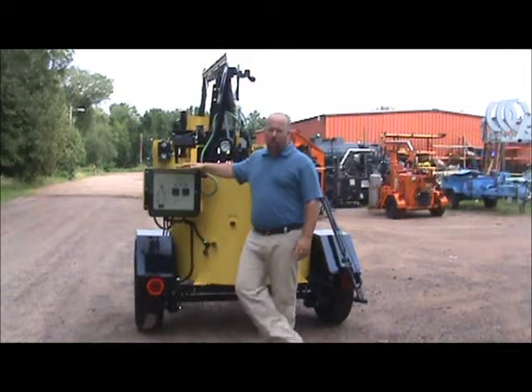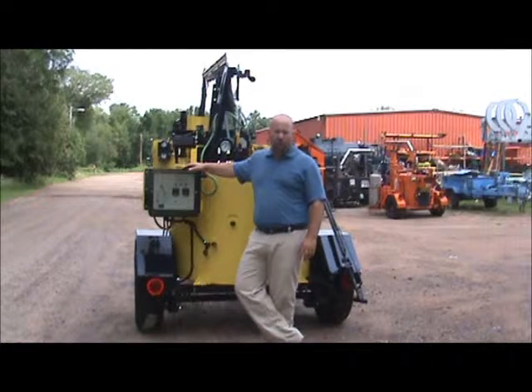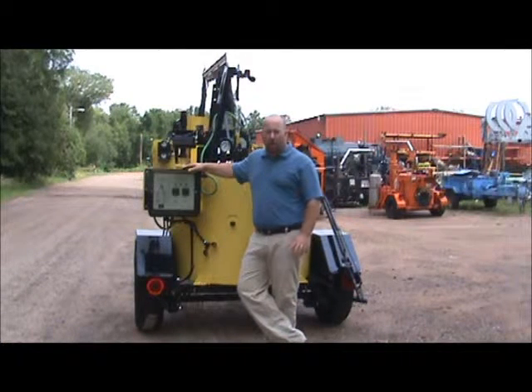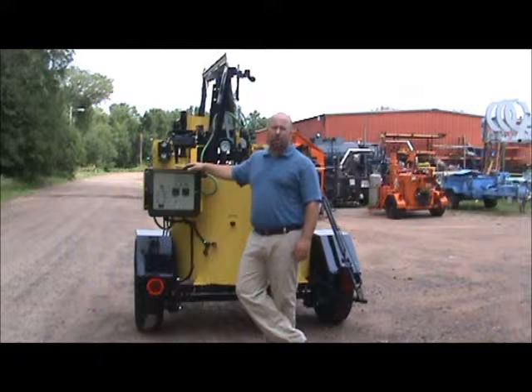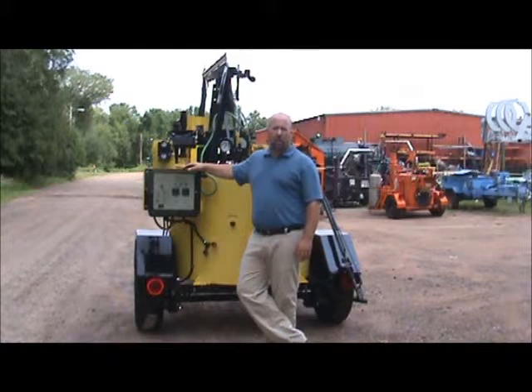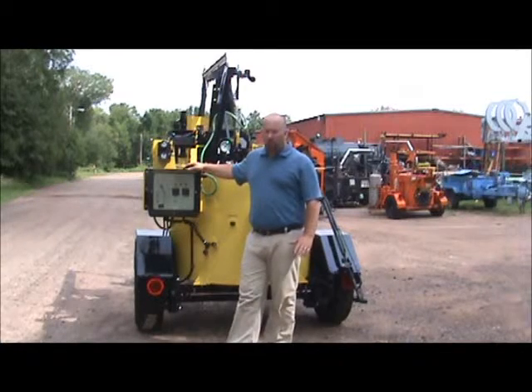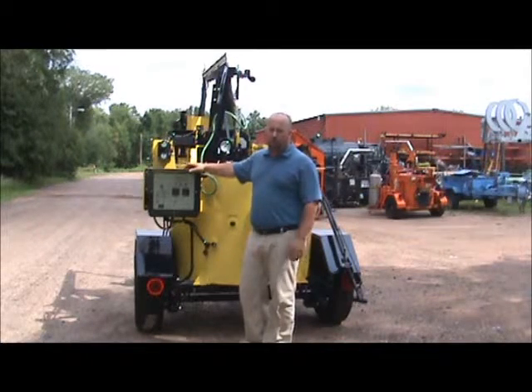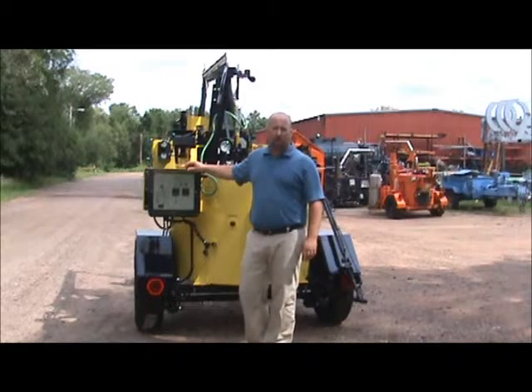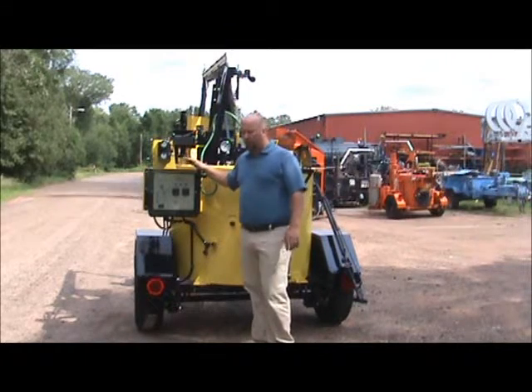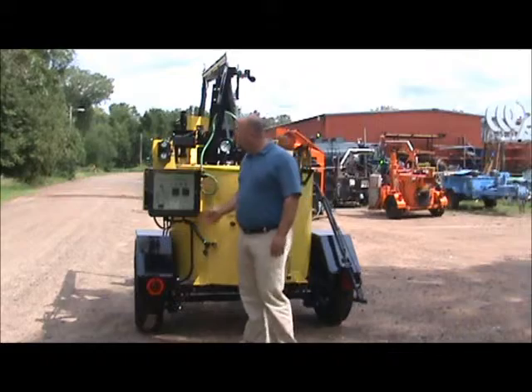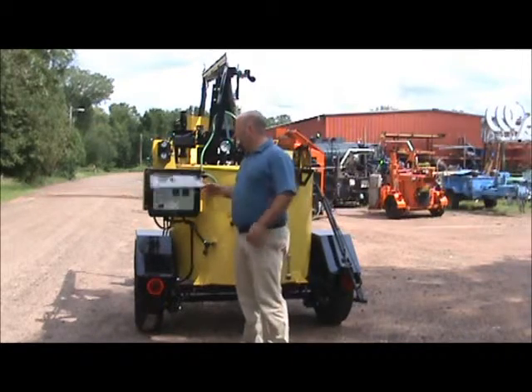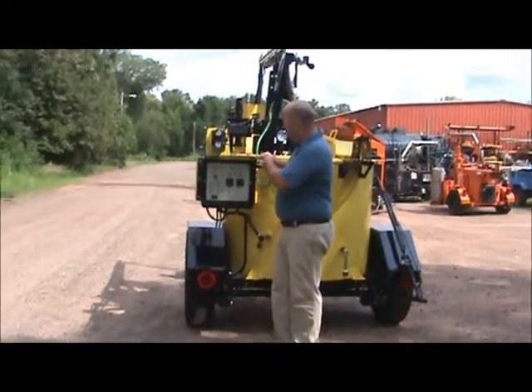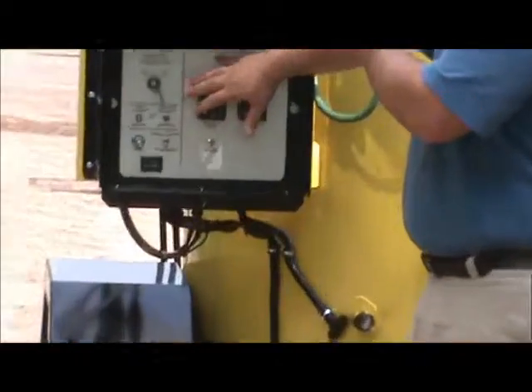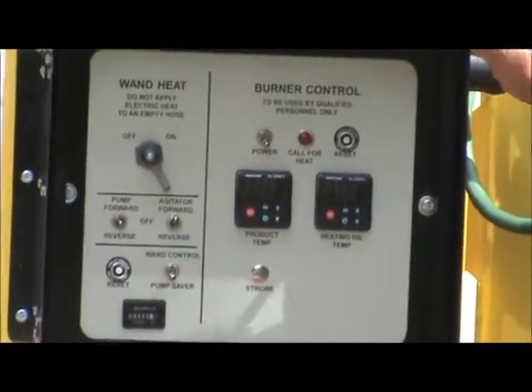Now, this unit's unique in the fact that we can fire it without the engine running. If you're going to do that for a long period of time, you do need to put a battery charger on the engine, because the diesel burner does operate off of the 12-volt battery. So you need to make sure that you have that battery charger on there, or have the engine running. The engine will maintain the battery if you're going to be firing for a long period of time. But we're going to go over the items in the control box first. The main burner controls are on this side of the control box. Again, very easy to operate.